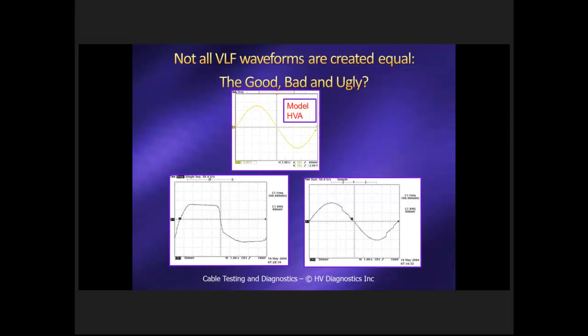There are different types of waveforms out there. You get a pure sine wave like you can see on the top. The bottom left-hand side is called the cosine rectangular waveform, which is acceptable from a withstand point of view, but it's very difficult to do any form of partial discharge testing with it.